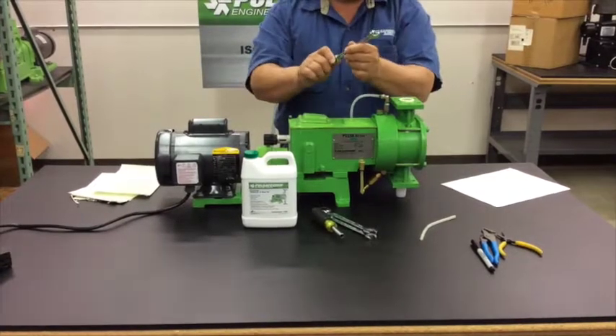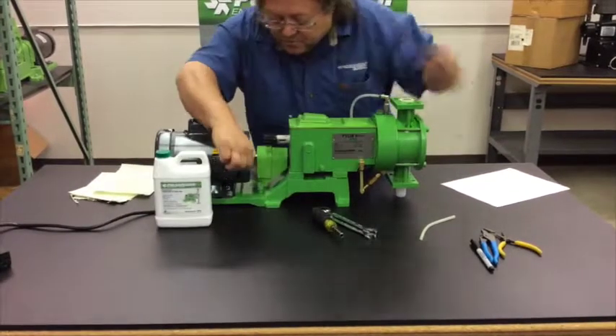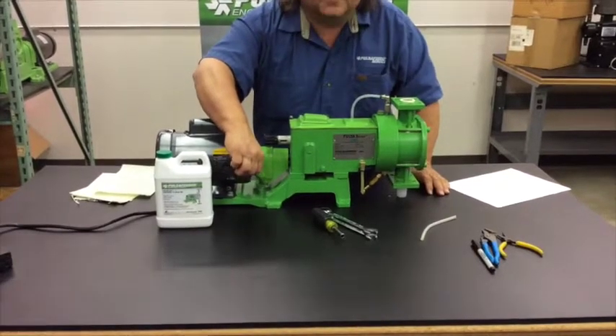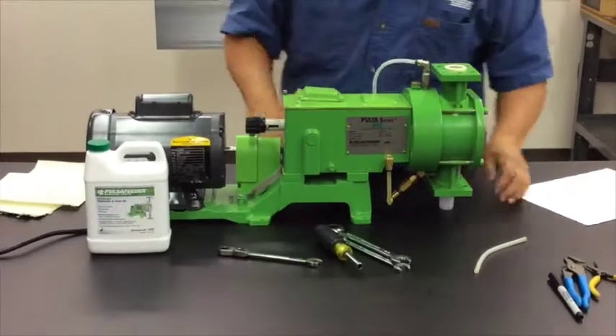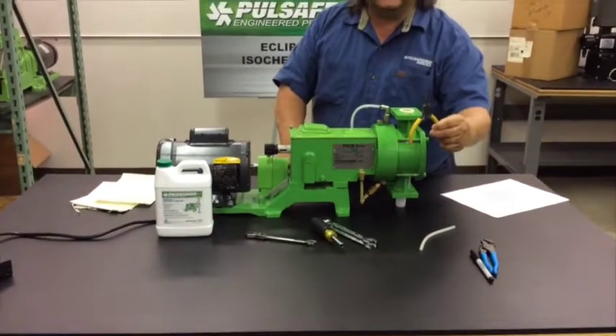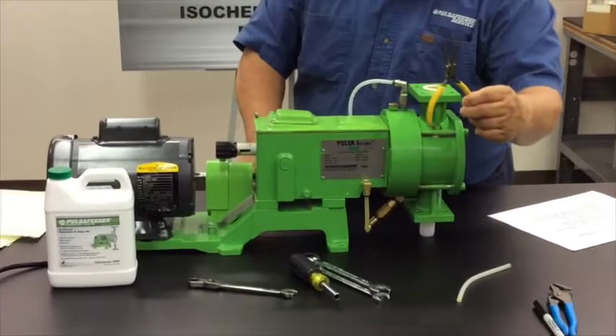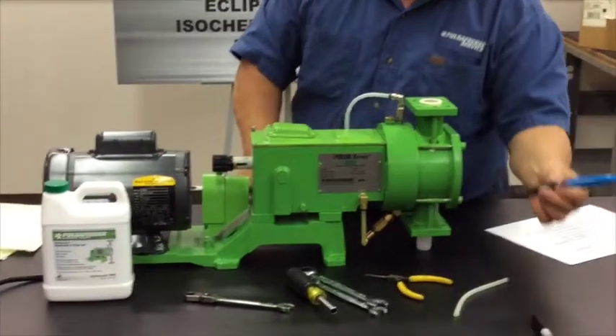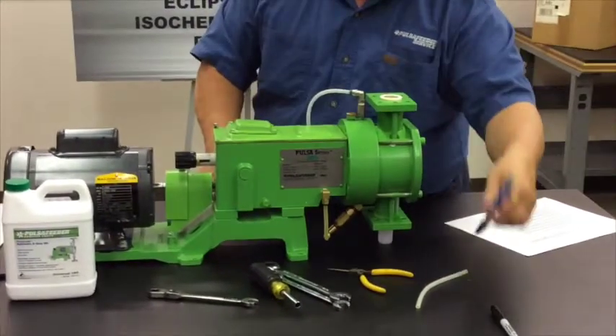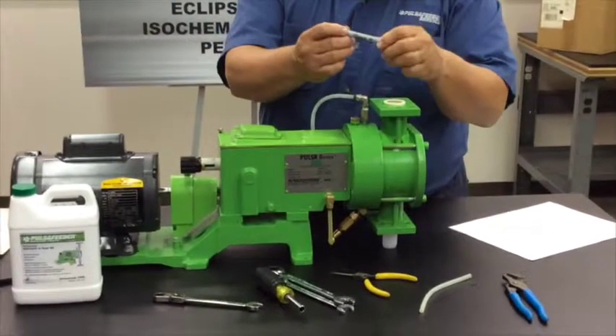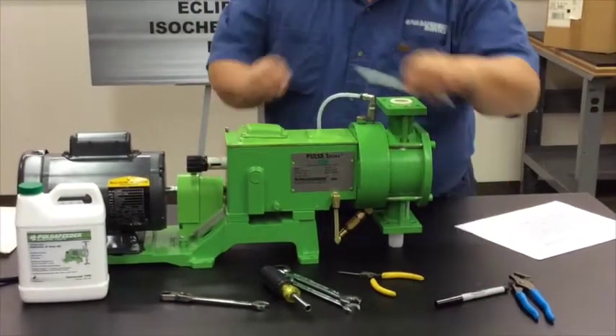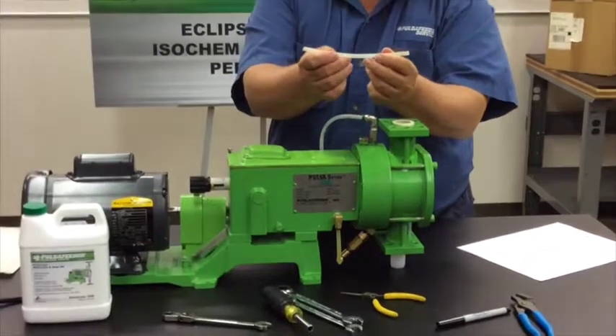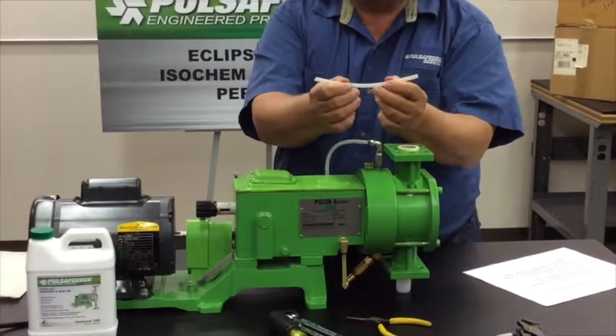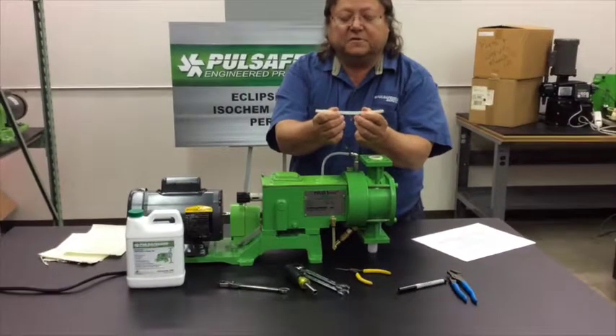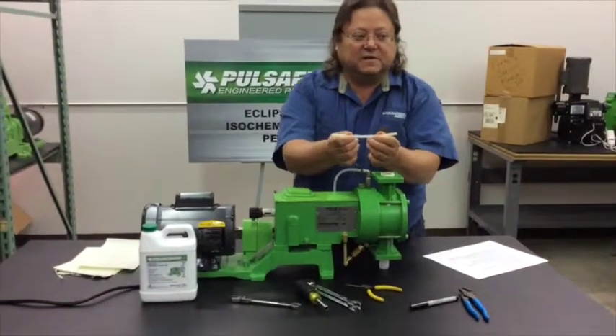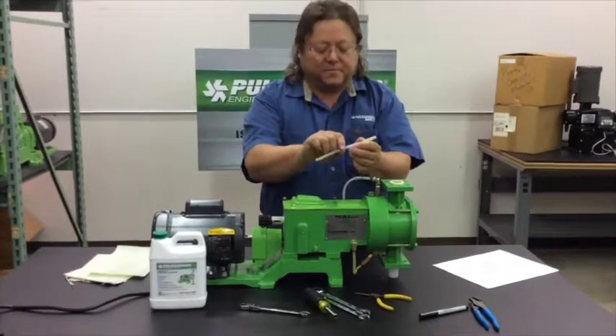I also have a 7/16 wrench to remove the nuts holding the coupling guard in place. I'm also going to be using a pair of fine needle nose pliers, an adjustable wrench, my marking pen, and lastly a short piece of polyflow tubing, 1/4 inch in diameter, that I'm going to use for diverting the flow from the hydraulic bypass vent into the sump of the pump.